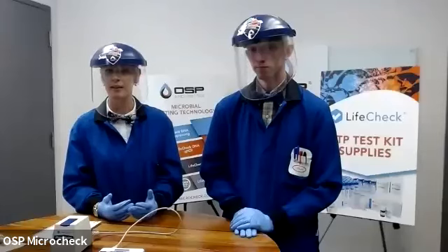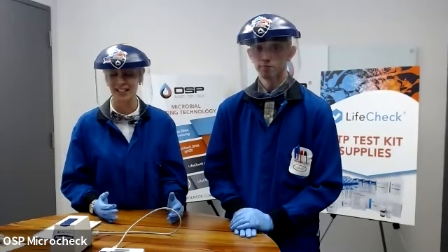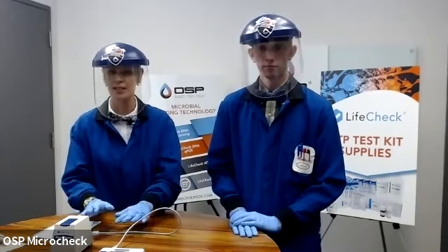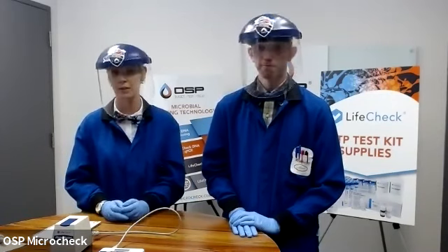Part of the reason is because our biocides are not selective. They will kill everything equally, which means that the amount that they're going to have to work and the amount of control that they have is going to be based on your entire microbial load. So using the ATP test kit to get a total microbial count before and after is the best test method that we would recommend. But absolutely, we can use it to evaluate any biocide application.